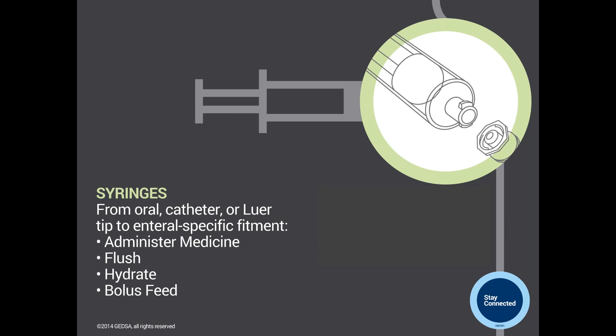One thing, as we were looking at the introduction of ENFit about the summertime last year, we had conversations with the clinical community and discussed the potential concern for dosing accuracy of small volume ENFit syringes. And that is due to the reverse gender orientation. This is something, by the way, that is consistent with what's in use outside the U.S., and I'll get to that in a second. But clinicians and pharmacists were indicating that dosing accuracy expectations were in the plus or minus 10% target range. From an industry perspective, we certainly looked at that very carefully and said we want to be able to accommodate that expectation or need.